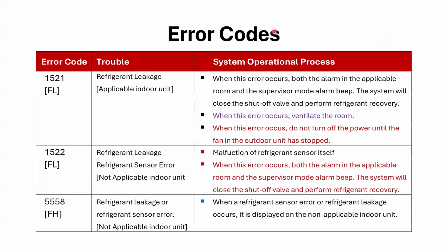Here's a list of error codes. So on the Smart Multi or one of the controllers, you can get 4 numbers, right? A 1521, you could get a 1522 or 5558. And on some of the other controllers, or if it's 1-to-1, you may get the letters, right? We just get a letter number combination like on the P series, like a P8, P6, whatever. So you might get FL, but it's the same code. 1521 at the outdoor, and you go inside and the controller's displaying an FL, that's the same code.